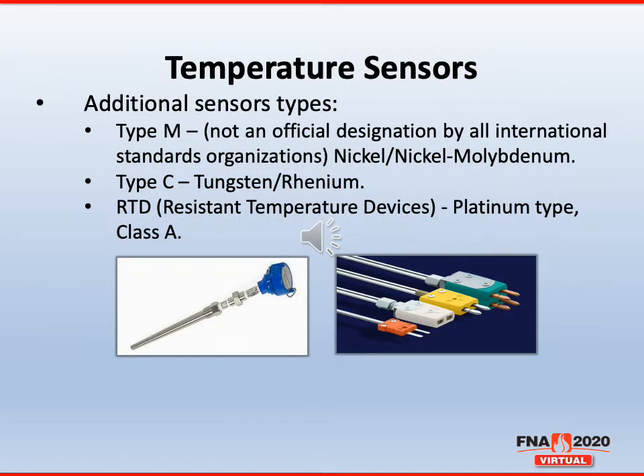Now moving on to some of the changes when it came to temperature sensors. We did add additional sensor types, type M, which is not an official designation by any international standards organization. It's a nickel-nickel moly thermocouple. We also added type C, which is a tungsten rhenium, also known as a refractory thermocouple. Another sensor that was added as well was RTDs, resistance temperature devices, though we only limited those to platinum type class A.